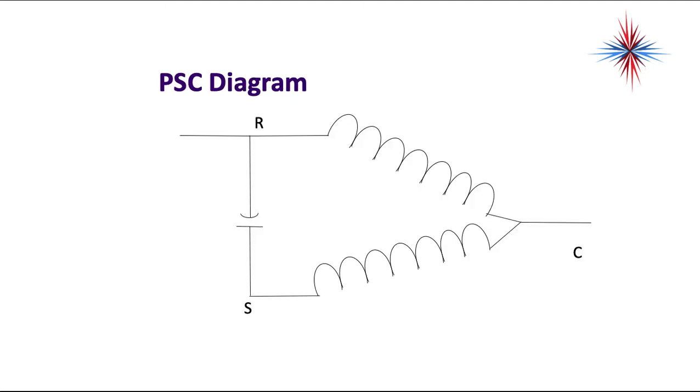A PSC diagram varies slightly from the split phase diagram that we looked at in the split phase video. We have our line voltage that comes in here and connects to the run winding, connects to common and back to neutral or line two depending on what your voltage readings are.